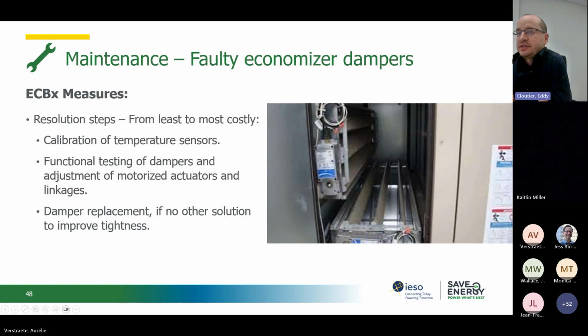So in that case, I would say that there are a few resolution steps from least to most costly. First, make sure that the temperature sensors are calibrated. Next, a simple functional test of the damper would show if the damper is operating properly and completely shut off during recirculation mode. And if nothing can solve the problem in another fashion, a complete damper replacement might be the ultimate solution.